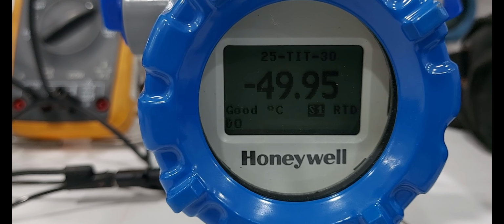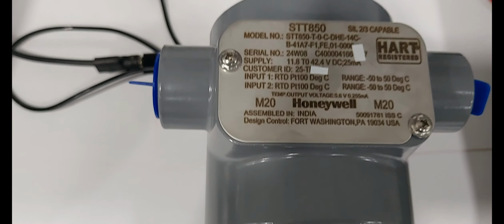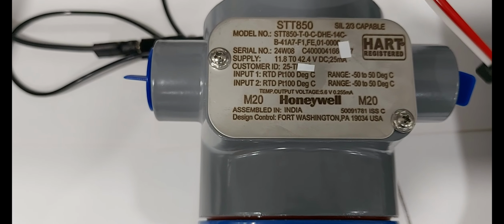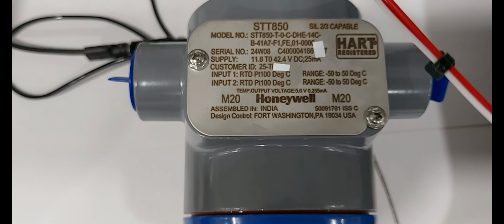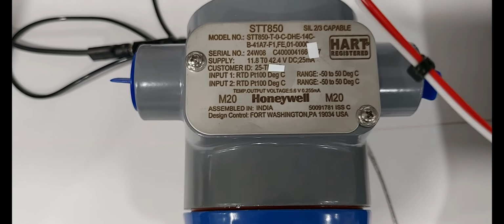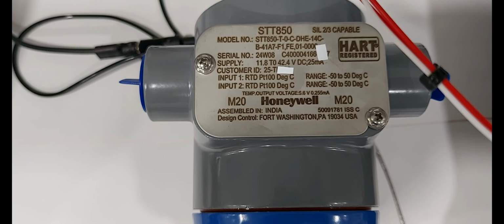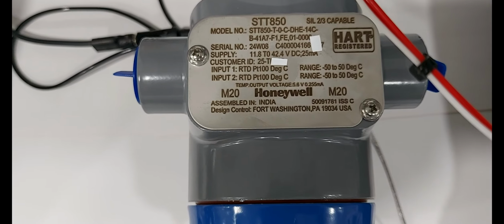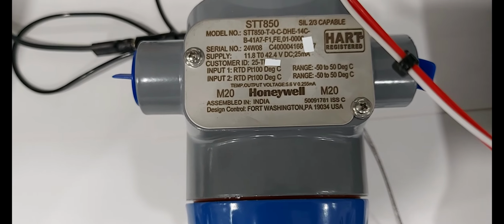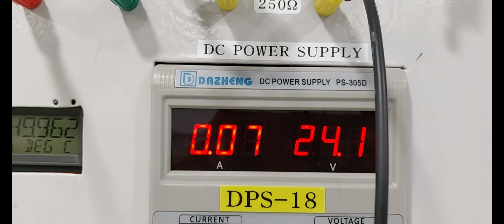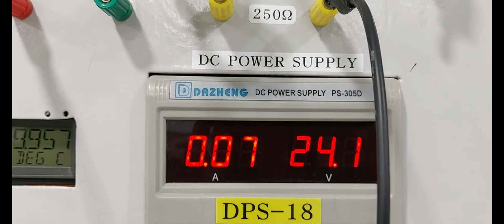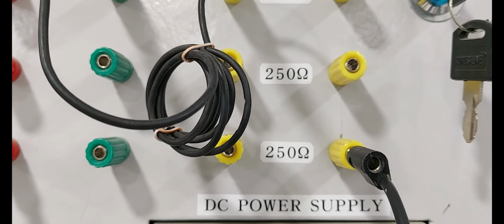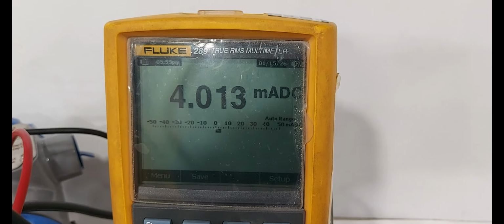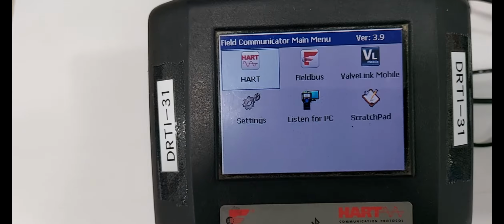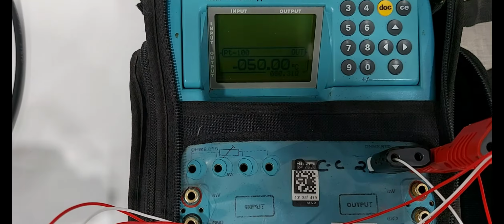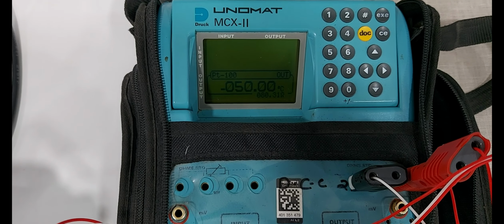Today we are introducing the Honeywell STT850 temperature transmitter calibration procedure. Communication protocol is HART protocol. The instrument range is -50 to 50 degrees. Minimum required equipment: 24 volt power supply, 250 ohms resistance, one reference multimeter, one field communicator and one multifunction calibrator.